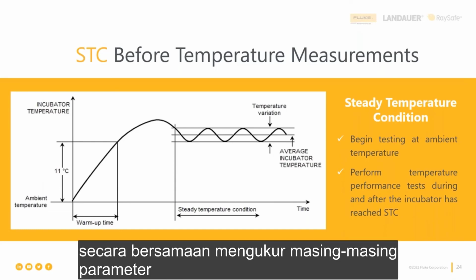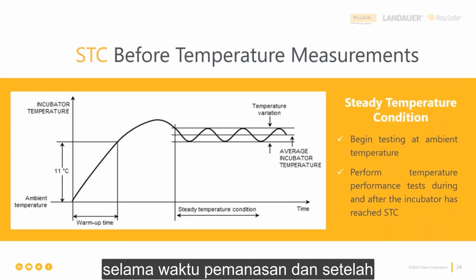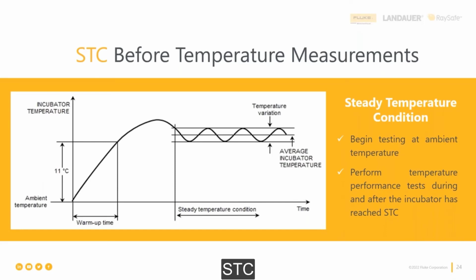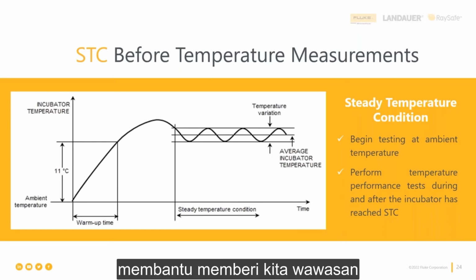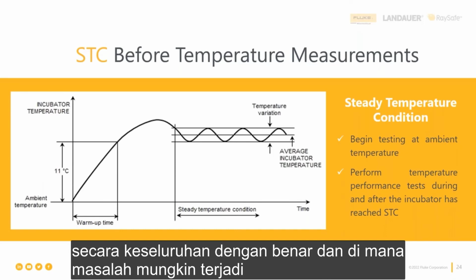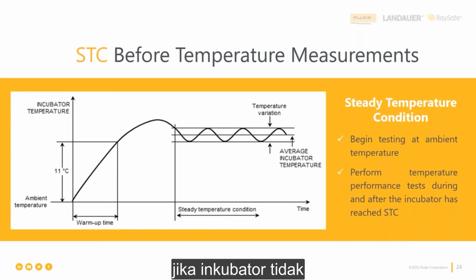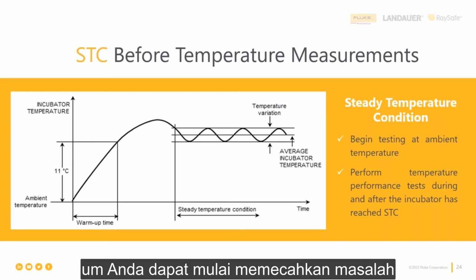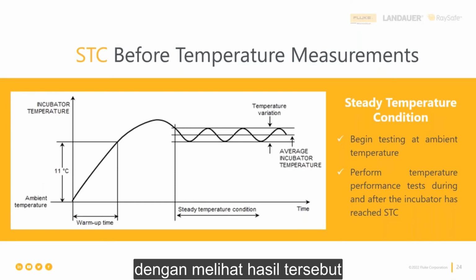Simultaneously measuring each parameter during warm-up time and after STC helps give us insight into how the device is running as a whole, right? And where problems might be occurring if the incubator isn't functioning properly. So it gives you a sense for, is it something with the fan? Is it something with the heating element? You can start to troubleshoot by looking at those results.